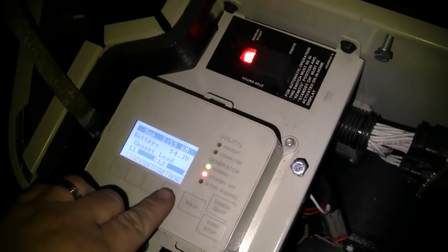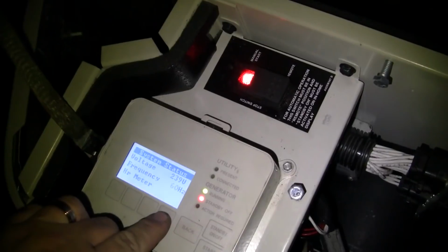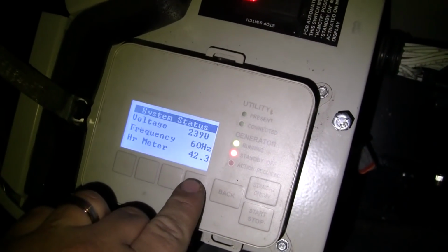Let's see how we're doing here. So we're right at 2 hours of runtime, and I'm happy with that. My limiting factor here is gas pressure. I can't get this thing right to 100% load on natural gas, but we're pretty darn close. What are we at now? 65.66 amps. So that's not bad. We've been there for a good hour and a half, I would say. So I'm going to call that good, shut the load off and end this test.